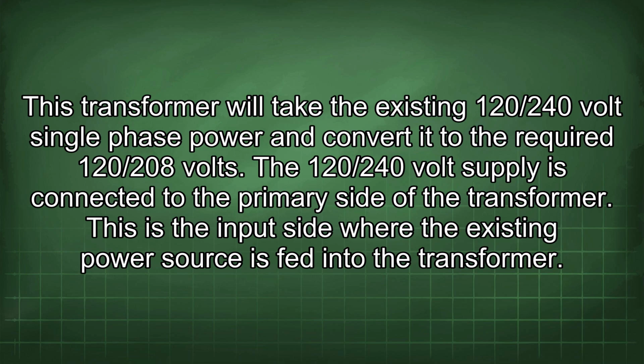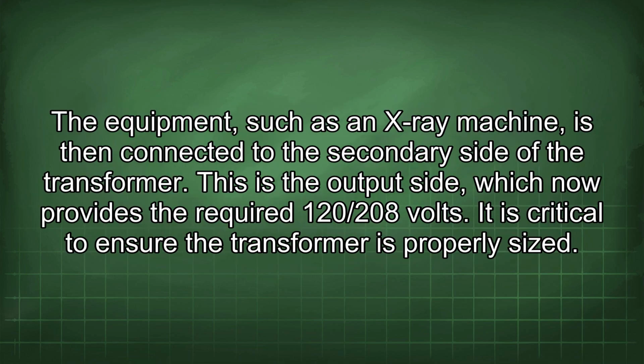The 120/240 volt supply is connected to the primary side of the transformer. This is the input side where the existing power source is fed into the transformer. The equipment, such as an X-ray machine, is then connected to the secondary side of the transformer. This is the output side, which now provides the required 120/208 volts. It is critical to ensure the transformer is properly sized.